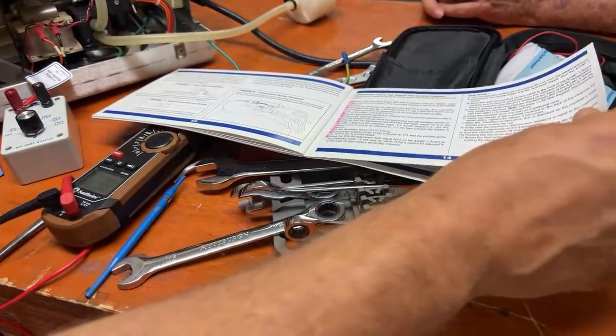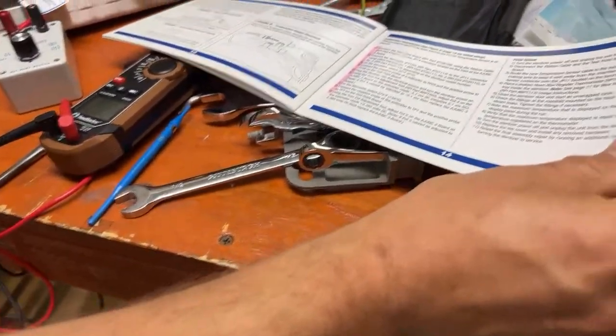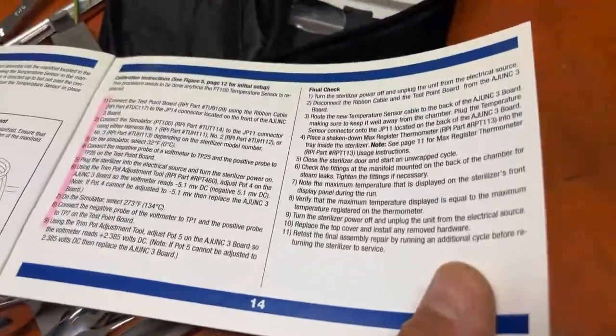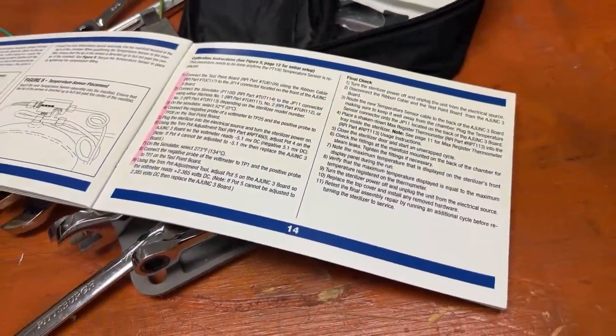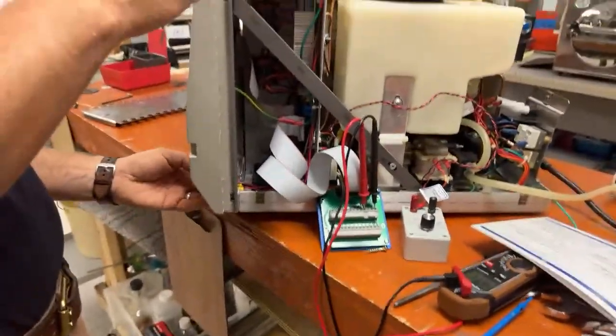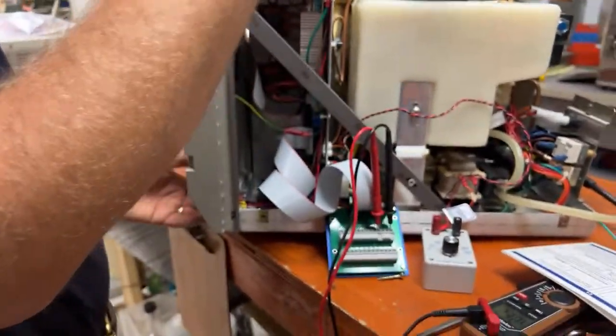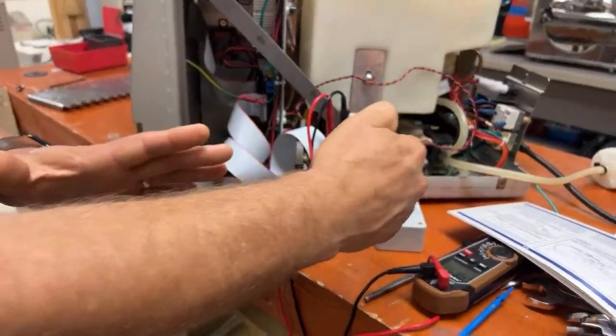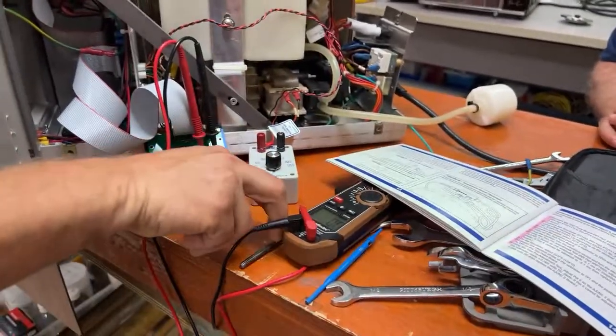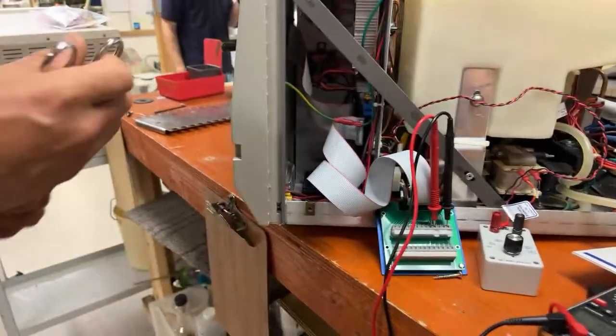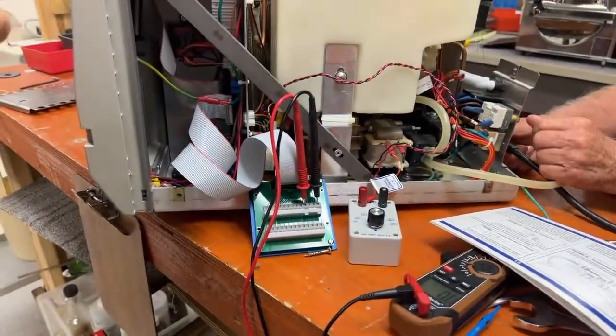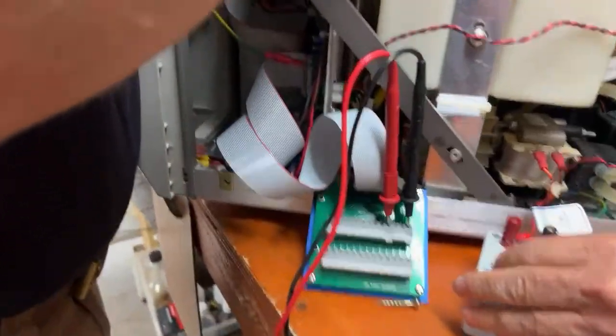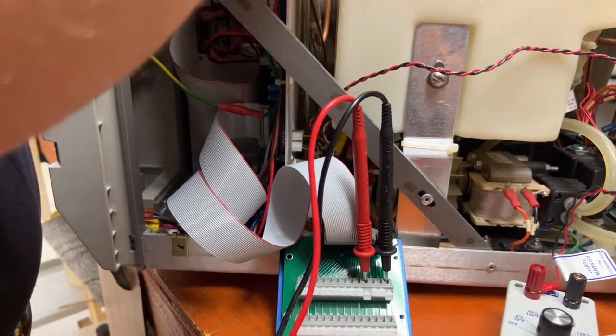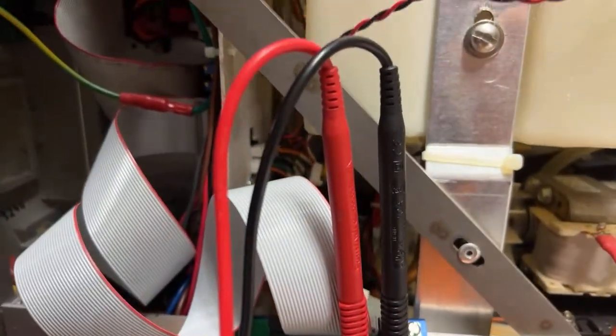So now, it doesn't actually tell us to rehook up the pressure transducer of the unit, but we're going to do that, because right now we've used this box and adjusted the 0 and the gain. So now we're going to use our same process. We're going to unplug the unit just so we don't short anything out. All right, and I'm going to pull out the little test box here. One click on the hemostats. Pull her out. Okay. Get that out of there.